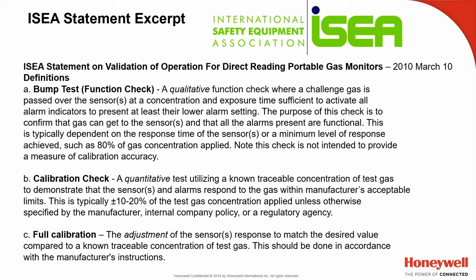But it's more of a go, no go or qualitative function check, where the challenge gas is passed over the sensors at a concentration and exposure time sufficient to activate all alarm indicators to present at least their lower alarm setting. And the purpose of this check is to confirm that the gas can get to the sensors, the filter's not clogged, and the alarms present are functional. You can hear them, you can see them, in some cases feel them, with the vibrating alarm.